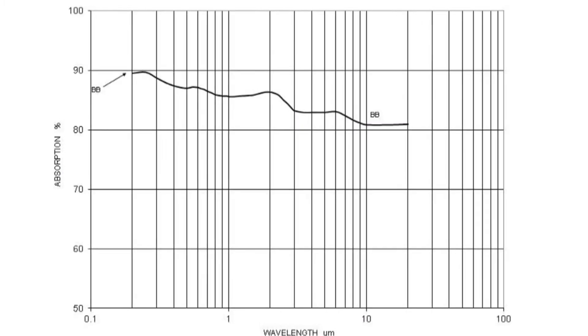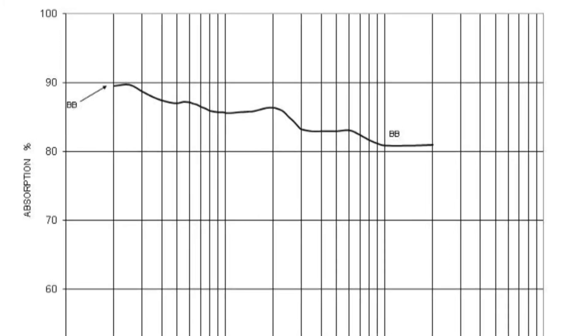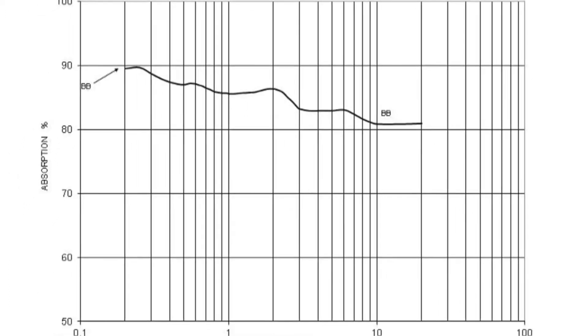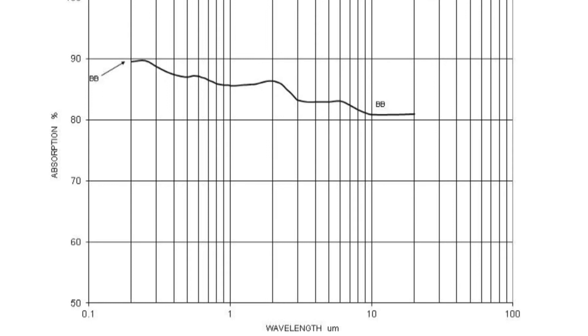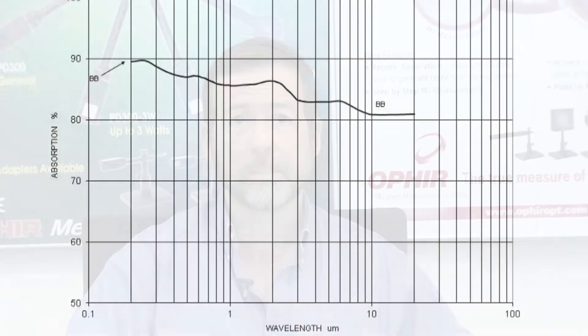The shape of a given absorber type's spectral curve is known and constant, since it's a function of the material of which the absorber is made. The relative response of a given absorber at a particular wavelength compared to the response at a specified reference wavelength is one kind of factor. Normally 1064 nanometers is the reference wavelength used for this purpose. The user does not see this factor, but it's in there — let's call that Factor 1.